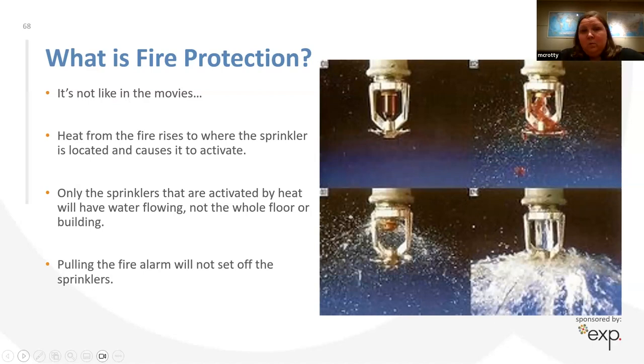It's not like in the movies. Heat will rise up to the sprinkler and cause it to activate, and then the water will flow. Only the sprinklers activated by heat will have water flowing. It's not like movies where someone sets one off and the whole floor is doused in water, or the whole building is raining down water and the main character runs through getting soaking wet. And it's not pulling the fire alarm and setting off all the sprinklers. The fire alarm will not set off the sprinklers.